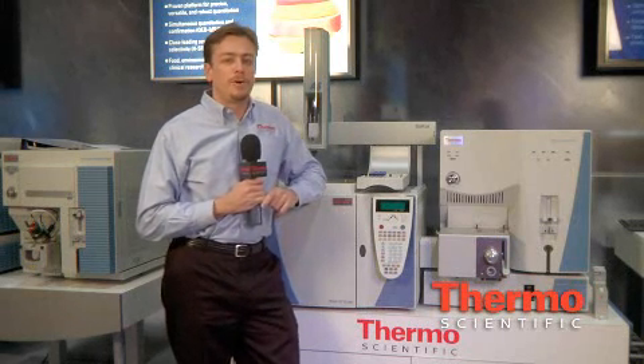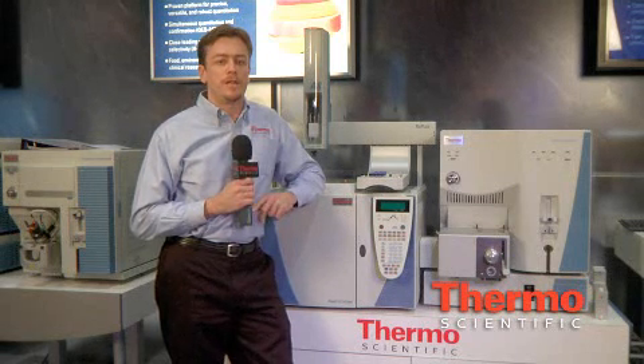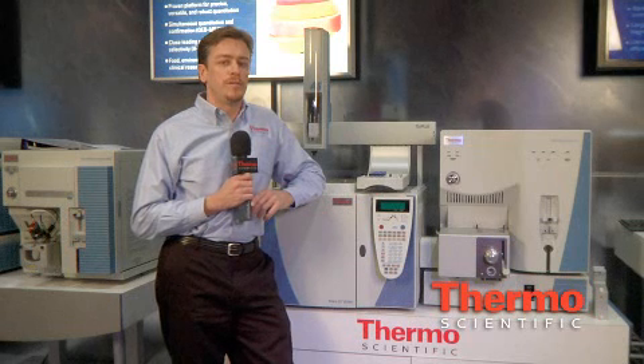Another functionality for all the mass spectrometers is PPINICI, or pulsed positive ion, negative ion, chemical ionization. This allows for the detection of both positive ions and negative ions in a single injection. Uses for this include PCBs and pesticide analysis.